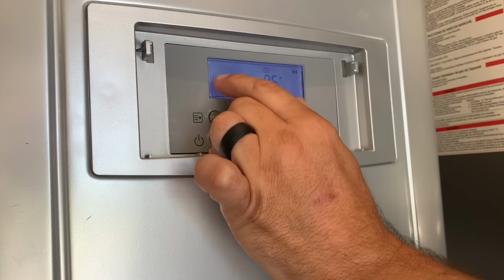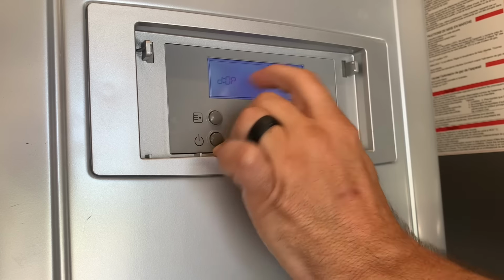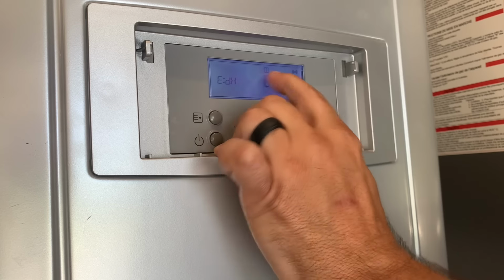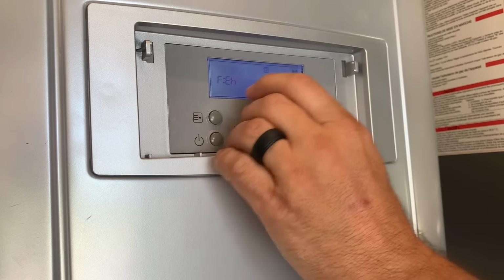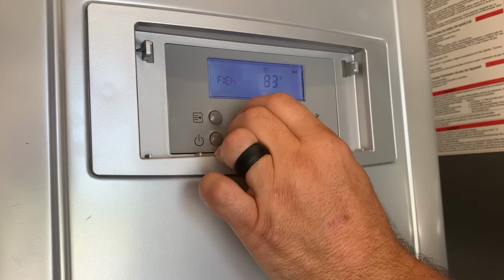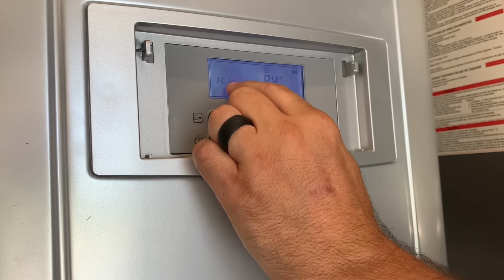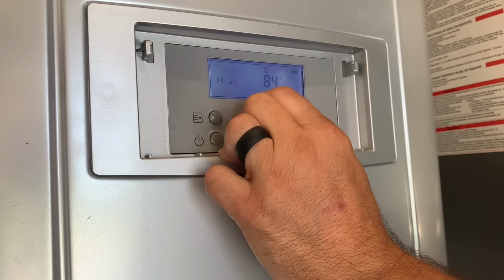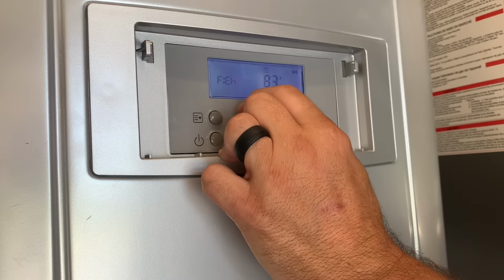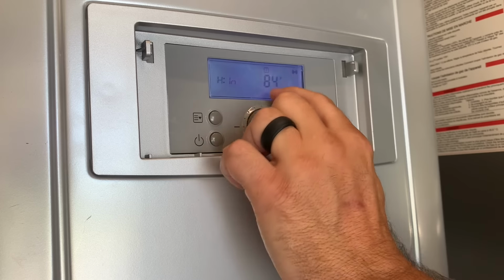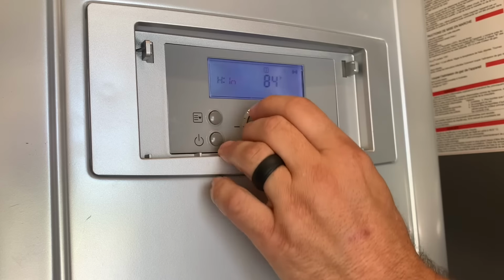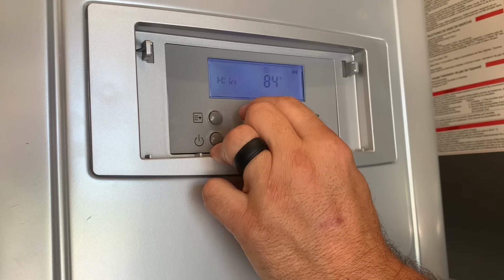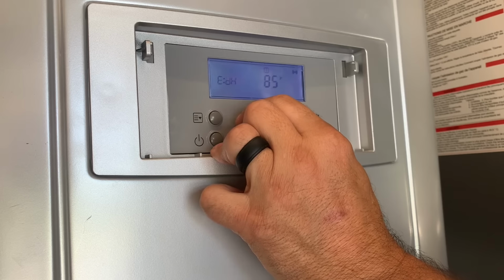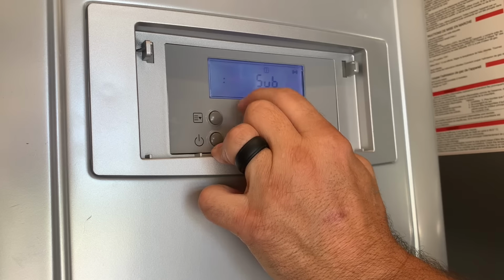DEFH. So we'll check DOP operating temperature. It looks like we're at 85. There's no water flowing through this. Exhaust temperature 83, that's just ambient room temperature, and 84. So this water heater is not currently hooked up to anything. It's just reading the ambient temperature of whatever water is in there, and the air temperature in the exhaust. So very important right here, easy to access.